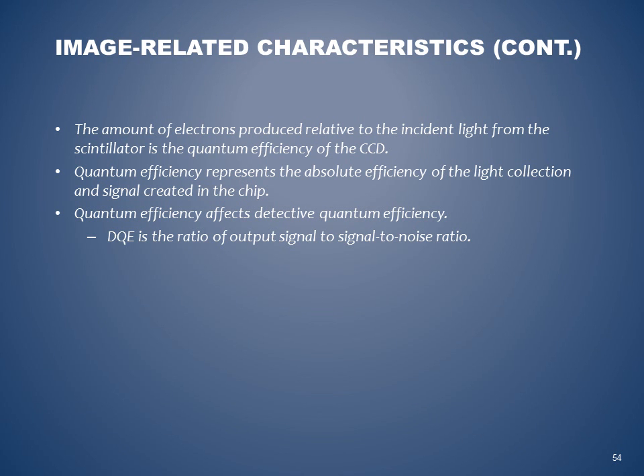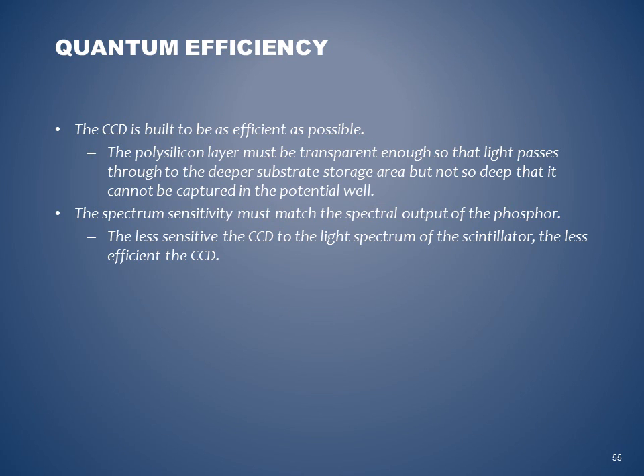The amount of electrons produced relative to the incident light from the scintillator is the quantum efficiency of the CCD. Quantum efficiency represents the absolute efficiency of the light collection and signal created in this chip. Quantum efficiency affects detective quantum efficiency. DQE is the ratio of output signal-to-noise ratio.